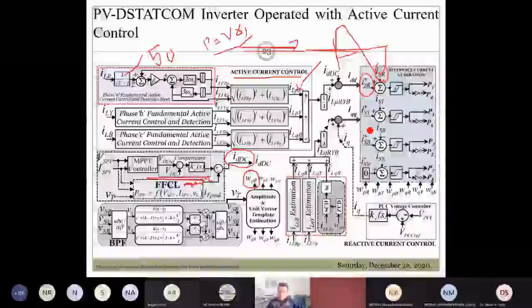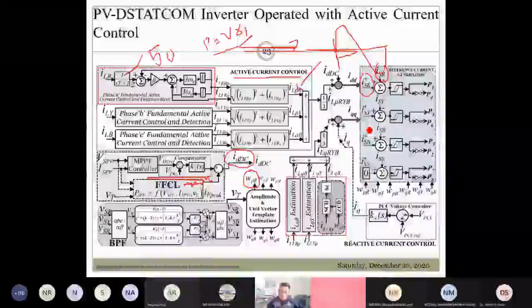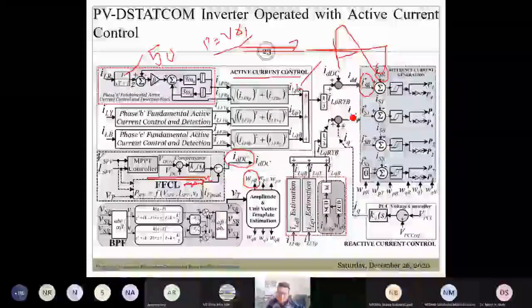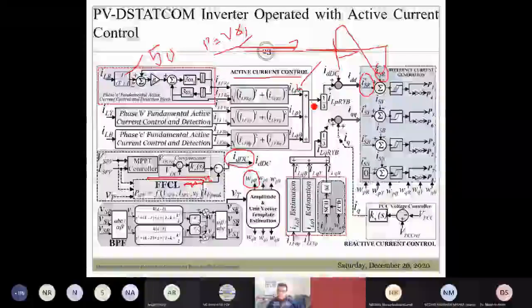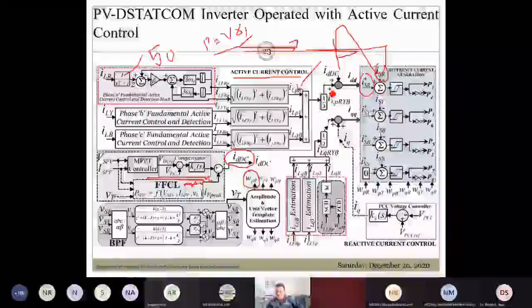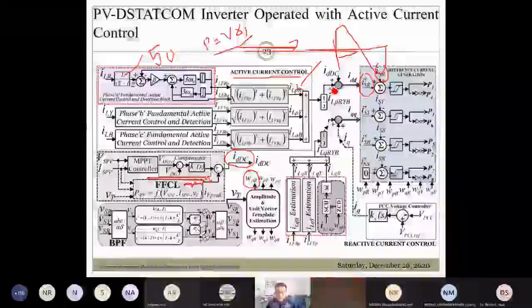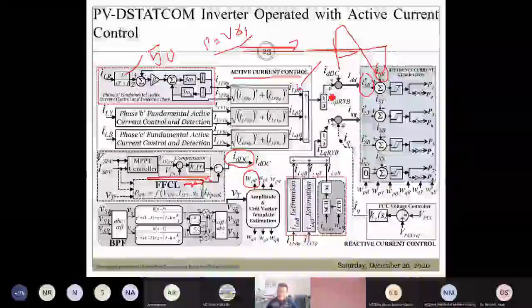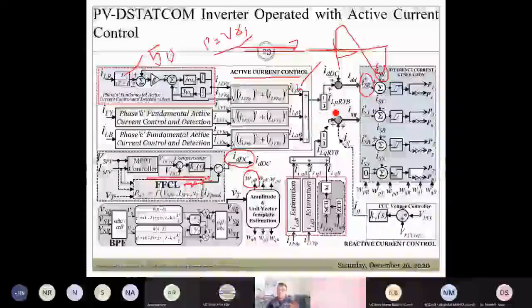Yes, sir. Okay. So as I mentioned, once the fault has disappeared, the power generation from the renewable energy sources will be ramped up. But you need to understand that this power generation in a ramp fashion can only be controlled in the upward direction. However, the downward ramp, the power reduction in the downward direction, cannot be controlled.